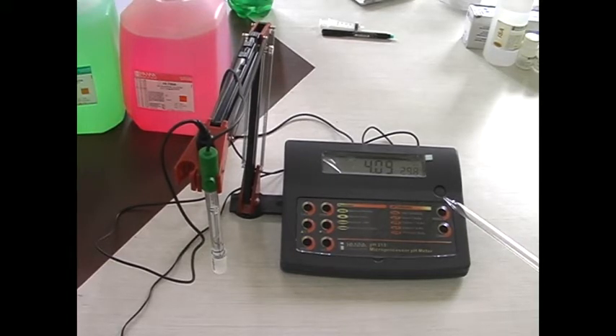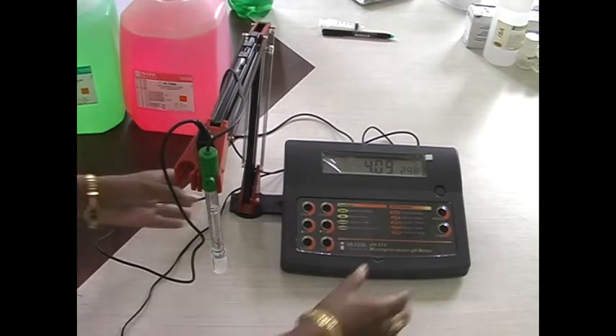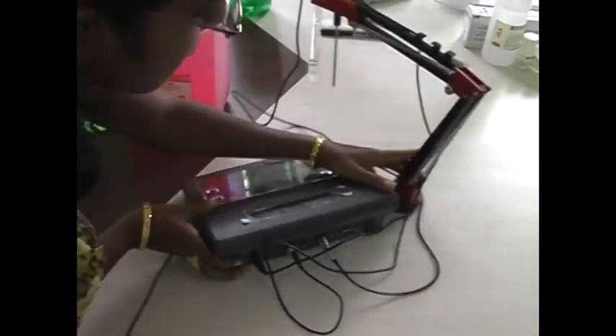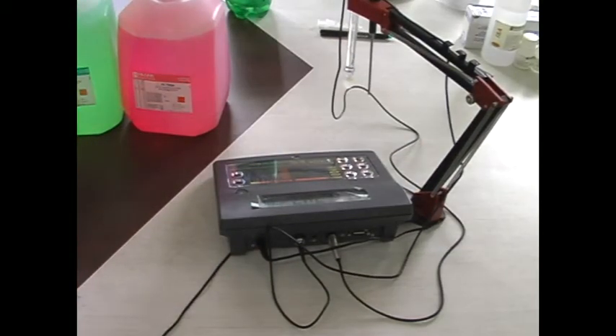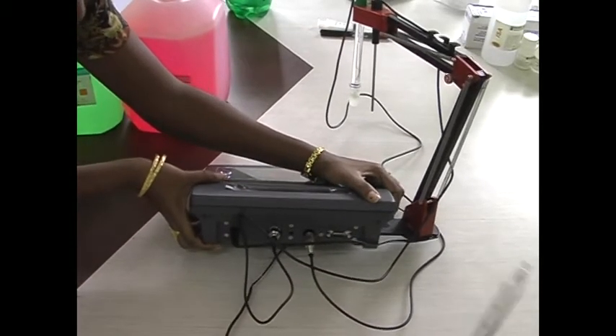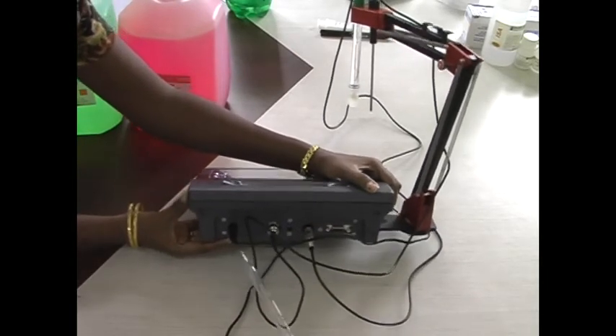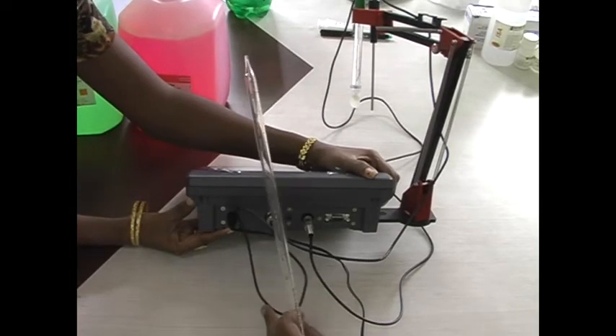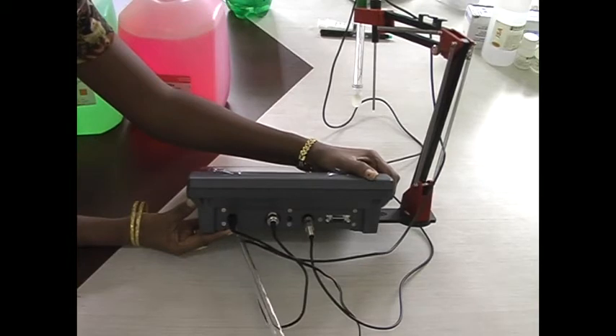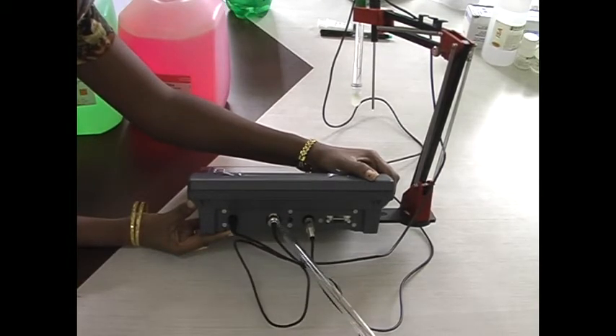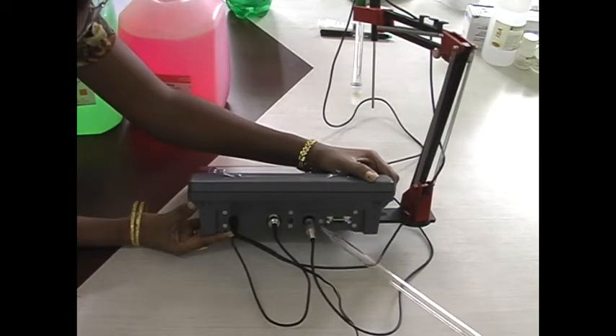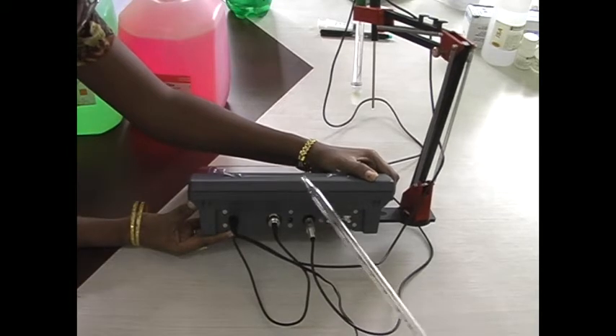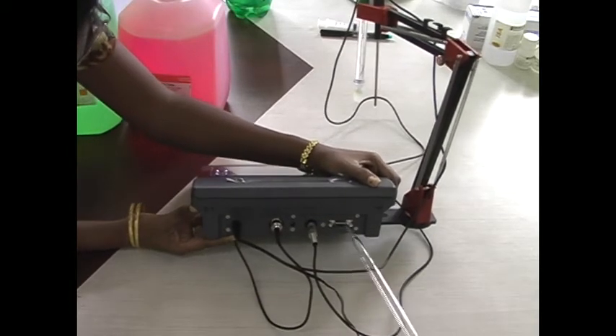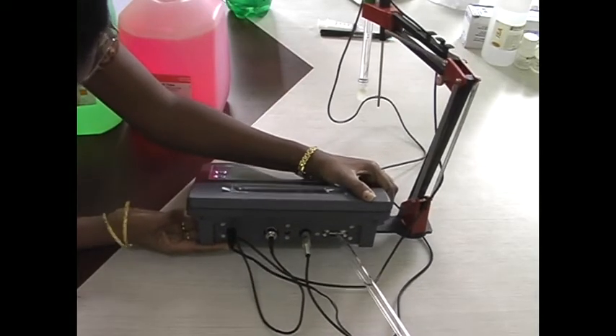Now we are going to see the rear panel of the instrument. The rear panel of the instrument has the 12-volt DC power adapter socket. This is the 12-volt power adapter connection. Then the BNC connection for the electrode. This is the temperature probe connection. This is for the reference electrode connection. And this is the RS-232 port. This is for PC connection.